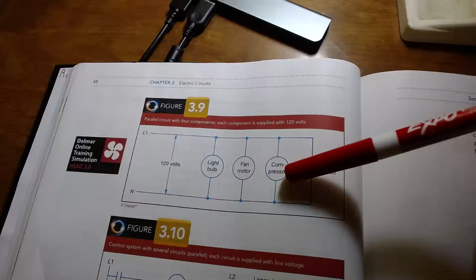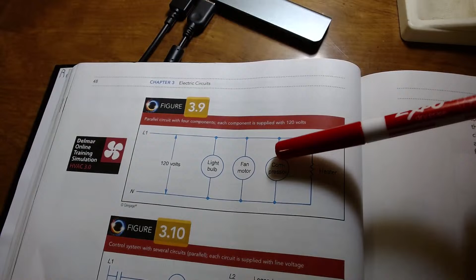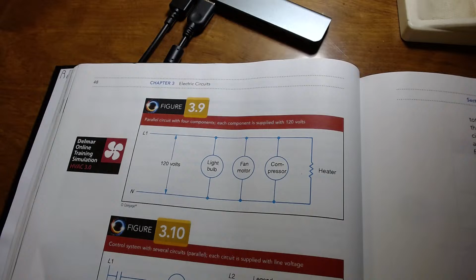Your condenser fan motor and your compressor are always in parallel with each other because when power is applied, they both come on. Okay. Your pressure switches on the schematics that we saw, the low and high pressure, those are in series because they start at one point, go from one switch to the next switch, and back to the end.